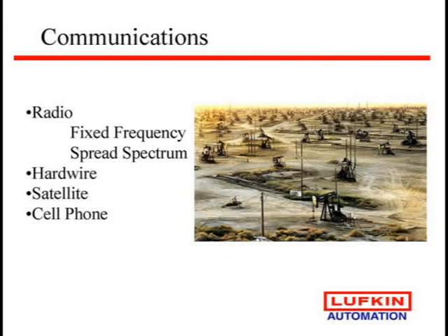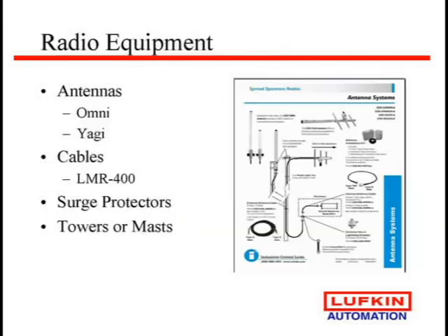And with that, they can calculate what they can do for a system. Now, normally you're going to have two types of antennas. An Omni usually looks more like a stick. That usually creates a round area or maybe an egg-shaped area that we can hit with the radio system. The Yagis are directional, and those usually go at the well site. And they create a band of about 35 degrees. So we've got to point that antenna at the base antenna.